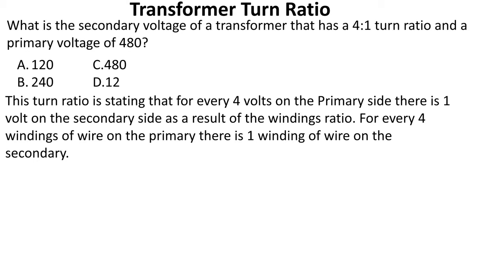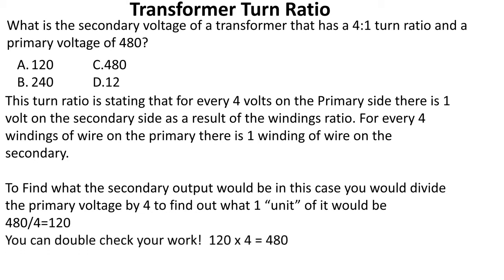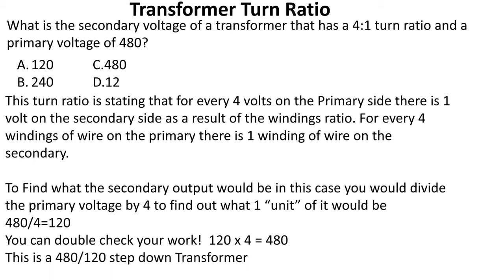This turn ratio states that for every four volts on the primary side, there is one volt on the secondary side as a result of the windings ratio — for every four windings of wire on the primary, there's one winding on the secondary. To find the secondary output, divide the primary voltage by four to figure out what one unit would be: 480 ÷ 4 = 120. Double-check by multiplying 120 by four to get back to 480. This is a 480-to-120 step-down transformer. We select A.